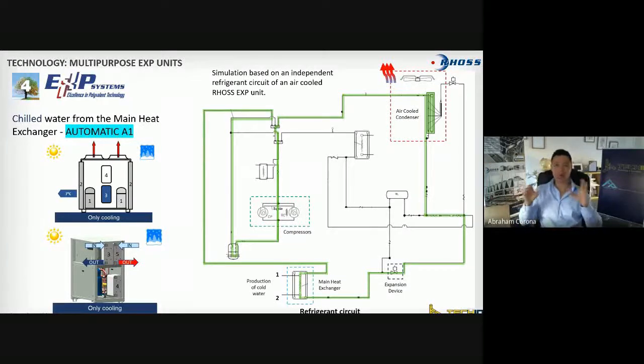At this stage, let's say we are in summer, this is probably an hotel or a building, and you only require cooling. Let's say you need to keep your water tank at 7 degrees, and you need to have your hot water tank at 50 degrees. The tank, we are satisfying that requirement. The water tank for the cooling is going to 8, 9, 10 degrees. The chiller picks up the delta T difference, and says, look, Ahmad, I need cooling. At that time, the chiller by itself will decide to run refrigeration circuit 1.